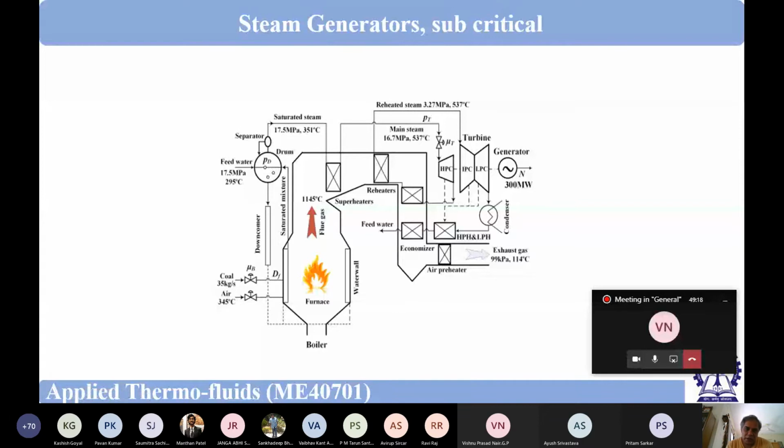Okay. So in this steam drum, basically we are producing saturated steam, but when the saturated steam passes through this water surface, it will contain a small amount of droplets, etc. So there should be some sort of separation, and this droplet should come back. We will elaborate this, and then this will go to the superheater.